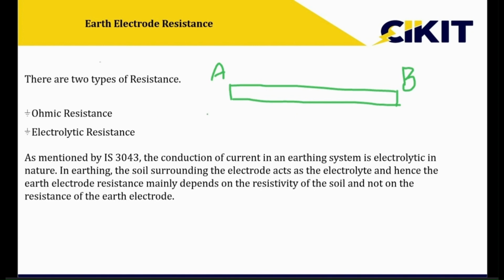This ohmic resistance does not depend upon the surrounding material. It depends on the particular material alone. The conduction takes place in that medium alone. Whereas in earthing, the dissipation takes place from the earth electrode to the surrounding environment. If this is the earth electrode, the conduction takes place from the electrode to the soil. So it mainly depends upon the surrounding medium. If the soil has very high resistance, then the earth resistance value will also be higher.